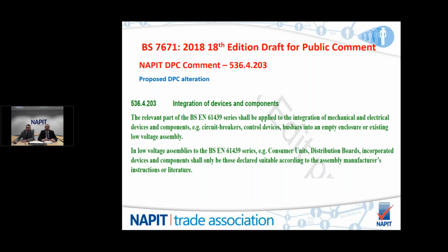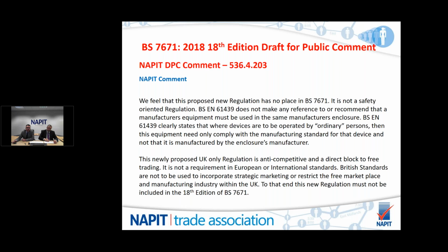Now that all seems quite innocuous, but it's actually got some quite significant repercussions as we go through this, and the industry will actually suffer if it gets in. So Frank can go to the next. So I'll comment on Regulation 536.4.203, which is a UK only regulation. We feel this proposed new regulation has no place in 7671. It's not a safety orientated regulation. BS EN 61439 doesn't make reference to or recommend that manufactured equipment must be used in the same manufacturing enclosure. BS EN 61439 clearly states that where devices are to be operated by ordinary persons, then this equipment need only comply with the manufacturing standard for that device, and not that it is manufactured by the enclosure's manufacturer.